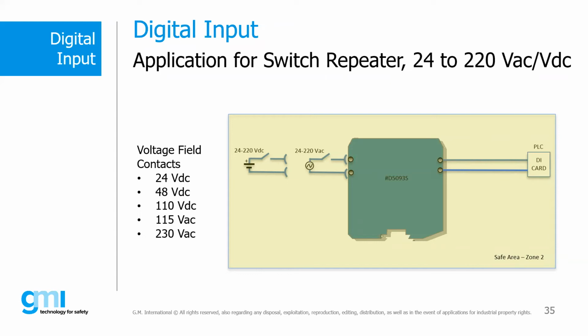What may be the main problem that can be encountered using a relay for this purpose? First of all, we have to keep in mind that usually a relay is designed to switch important values of current, while usually towards a digital input system, the currents in play are very low, typically less than 100 milliamp. In this situation, we can face problems of oxidation of the relay contact. Therefore, it's essential to choose a safety relay with gold plated contacts, which allow switching thanks to their high conductive performance, even at currents lower than 10 milliamp.